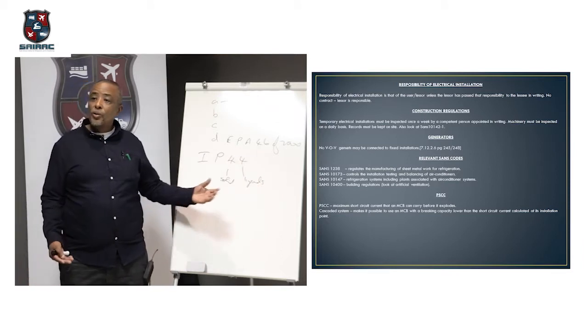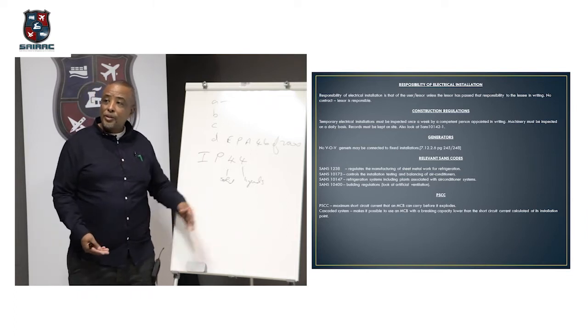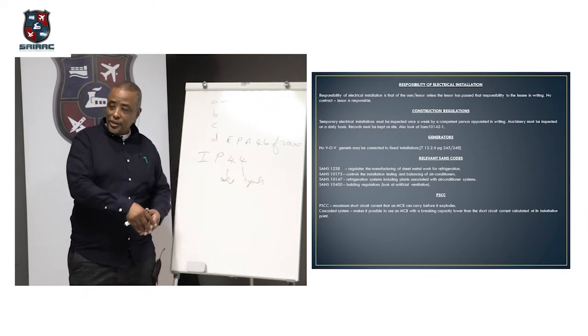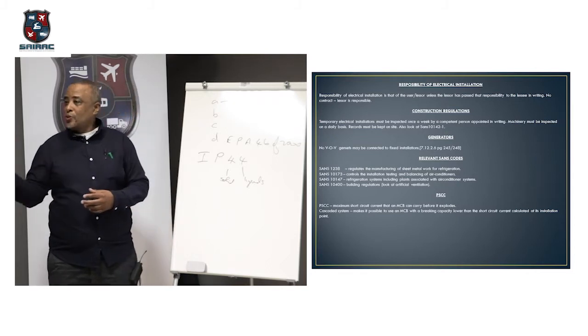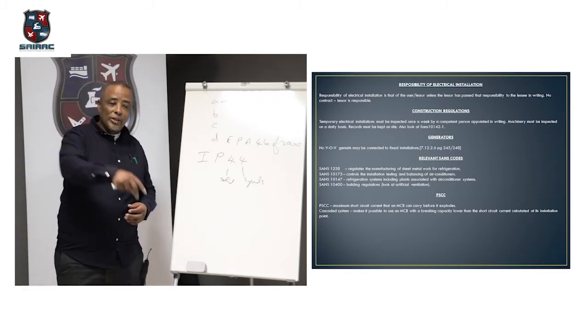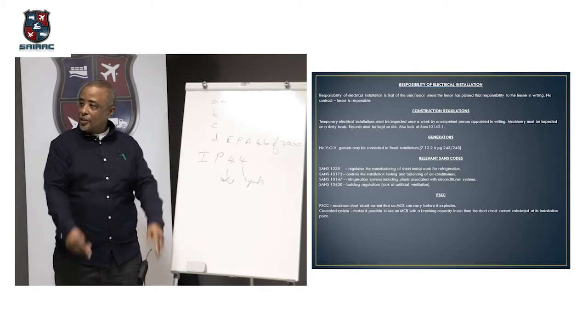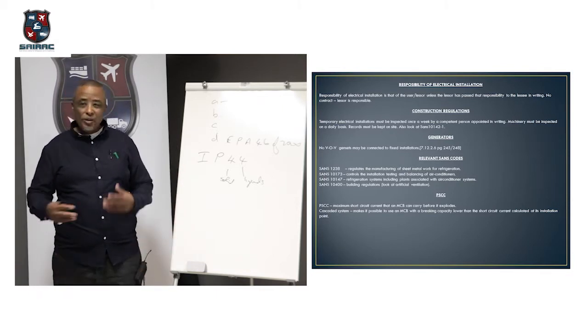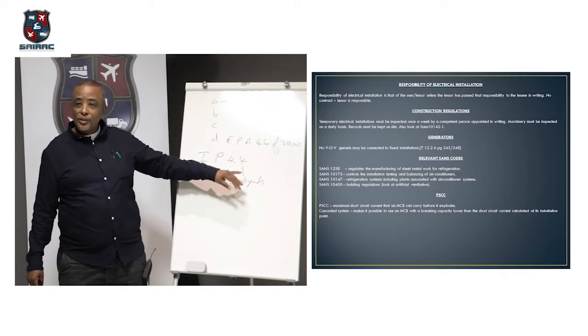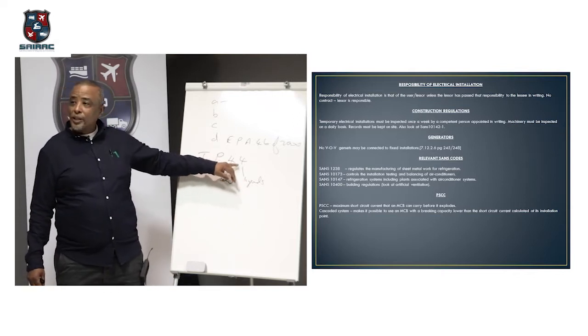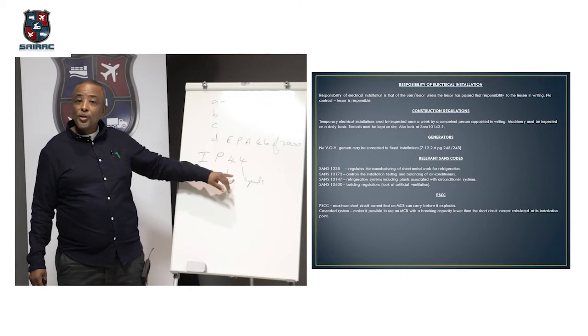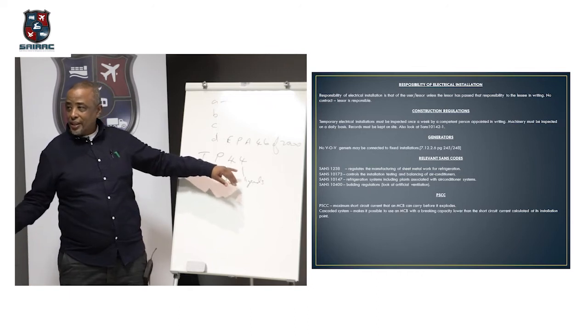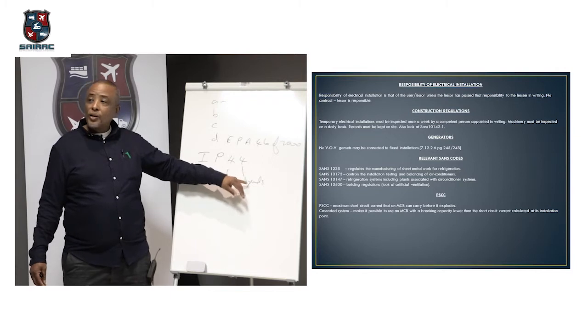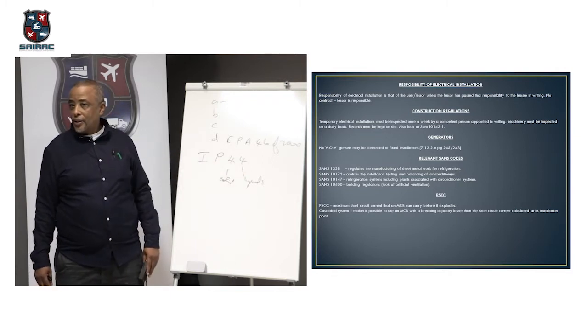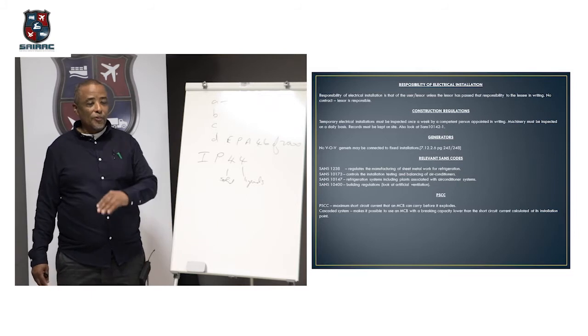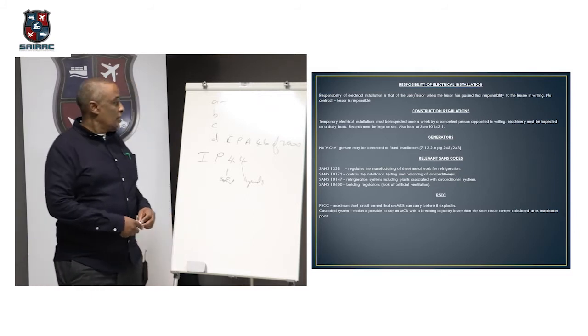Okay, so it's very important to know your environment to choose. And the table is there for you to look at the degree of splashing. Is it coming from this angle and that type of thing? Is it going to be immersed permanently in the water? So you've got to know. Okay, so that's what IP rating means: ingress protection. The first number denotes penetration of solids. Solid is dust, generally. And the second one is liquids. Okay, flame-proof, EXD, EXP, different story.